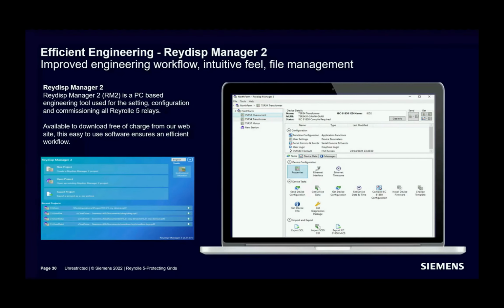Now, Reydisp Manager 2. Of course, it allows the user to configure and commission all Reyrolle 5 devices, supporting both local communication, via the USB port, and remote communication via the Ethernet port. And an important point here: Reydisp Manager is completely free of charge and can be downloaded from our web server.